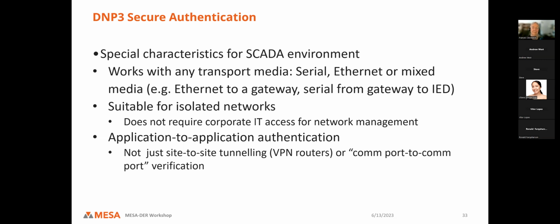So we could transport DNP3 across any media. It could be serial, it could be Ethernet, or it could be a mixed system that goes serial to radio, across to a radio receiver, and then Ethernet over a part, and then converted back to serial, or so on. So we have to have the end-to-end security across whatever that media is.